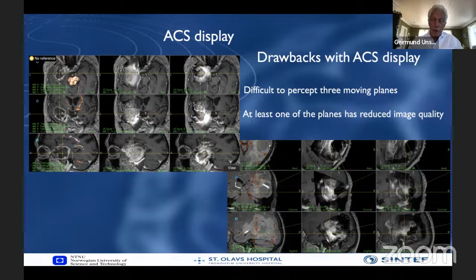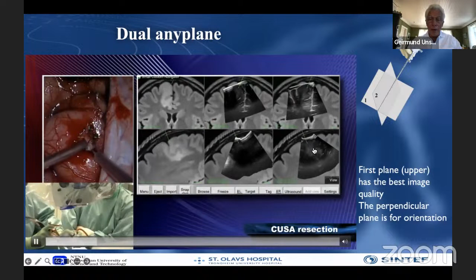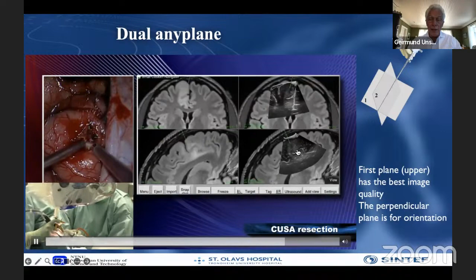The probe has an axial and a lateral plane that is the best, and the elevation plane, the thickness of the image, is usually rather too thick to make a good 3D ultrasound image. So we should be aware of that when we are using our display techniques. One technique is to use this dual plane, where this upper image is more or less parallel to the probe that has acquired the image. And then you have an orthogonal plane perpendicular to that plane, more or less for orientation.